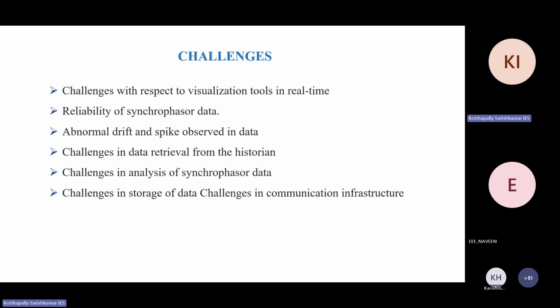And there's the reliability of synchrophasors, because all these PMUs are connected with a communication network of optical fiber. So if the fiber network is down, you will not get data from the synchrophasor. This is one challenge we are facing. For example, if you take 100 PMUs, you will get data from 90 to 95 most of the time. At least 4 to 5 PMUs, we are not getting data, not because of a PMU problem, but because of a communication problem. And sometimes, because of certain disturbances, we find abnormal drift or spikes in observed data, due to some loose connection or interference with nearby data.